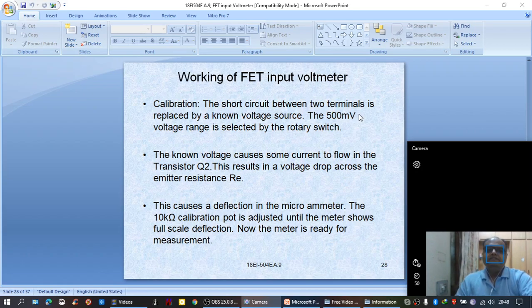Similarly, with the 5 volts range, the same procedure can be used, and the pointer has to show the full scale value. In any one position, this span adjustment is sufficient. That is, adjustment of the 10K pot to full scale position. Naturally, if it is set in one switch range, either 0.5 volts or 5 volts or 50 volts, in the remaining positions also it has to show full scale. If at all it is not showing, slight adjustment may be required. Now the meter is ready for the measurement.